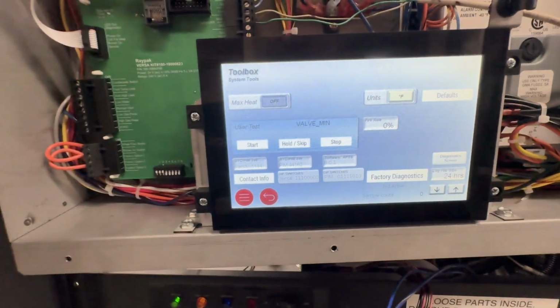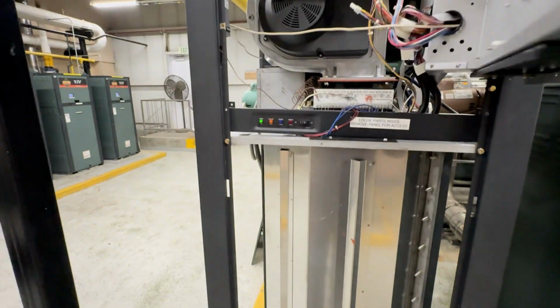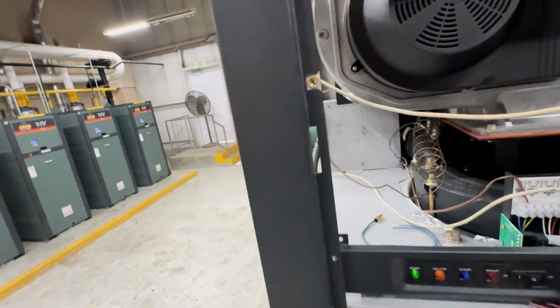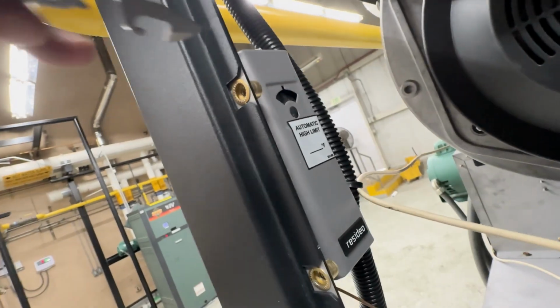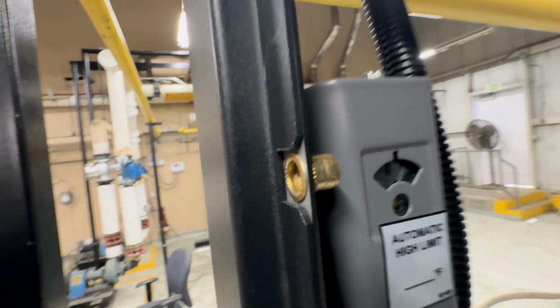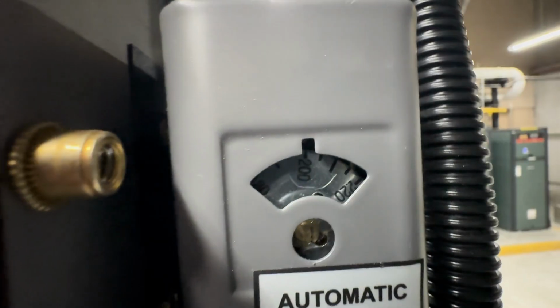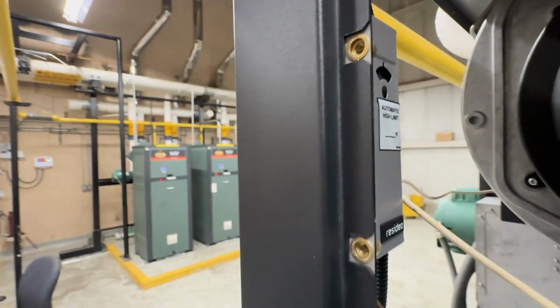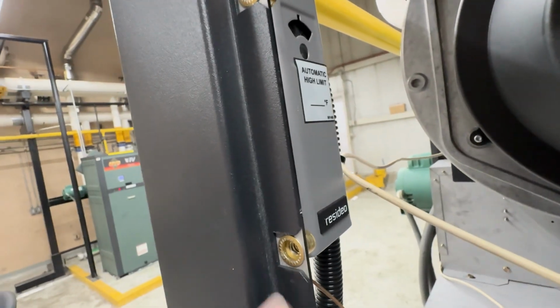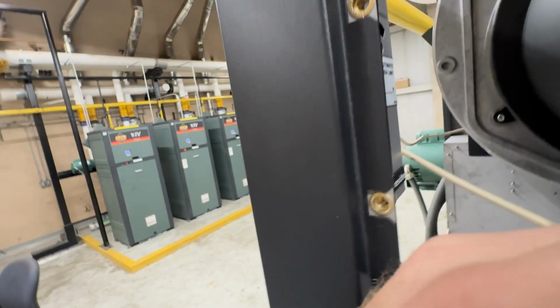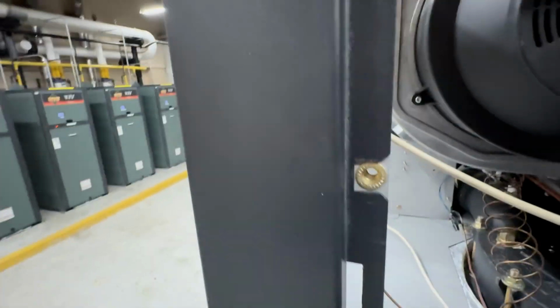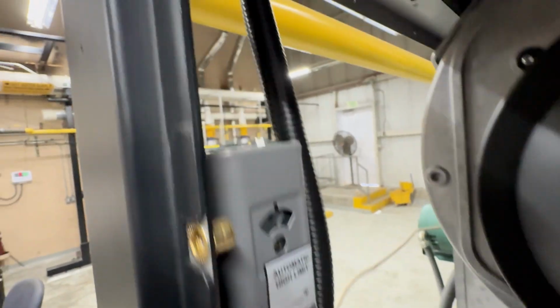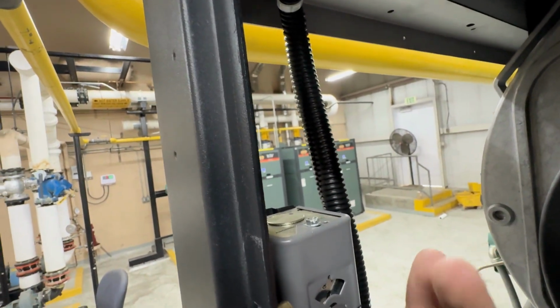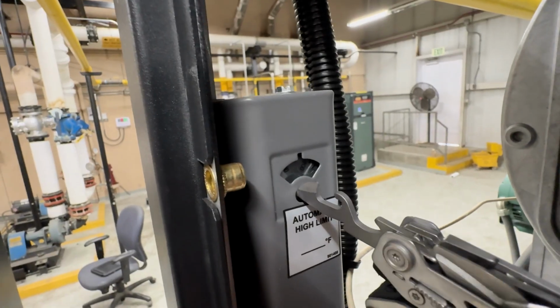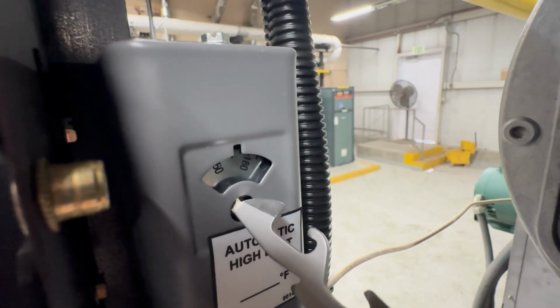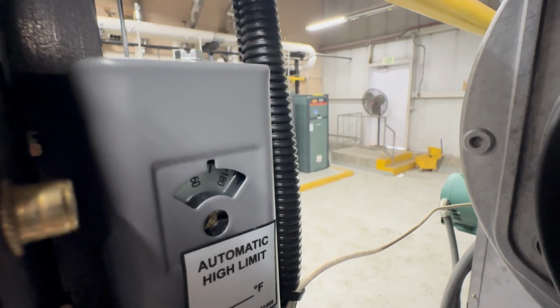While the boiler cycles through the test, the next safety we're going to test is up here to the left of the casing. This is our automatic high limit. It's currently set at 200 degrees. We're going to lower that to 170 and verify that this unit trips once it hits that outlet temperature. 170.